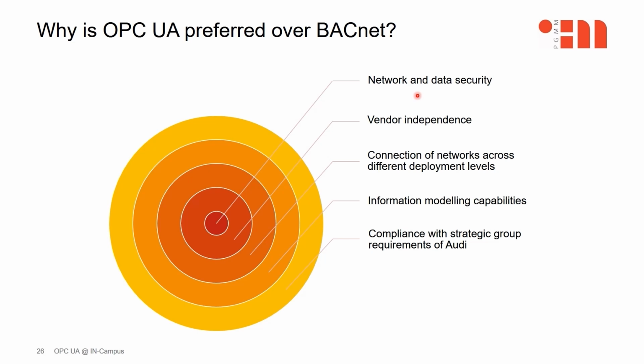In contrast to BACnet, OPCUA provides the cryptographic mechanisms required for a secure factory to safeguard communication. This is also confirmed by the investigations of the German Federal Office for Information Security, which systematically analyzed OPCUA communication with regard to the secure channel session and discovery services in accordance with the specification. This analysis did not reveal any systematic errors. Based on the analysis results, the OPC Foundation has further improved the OPCUA specification.